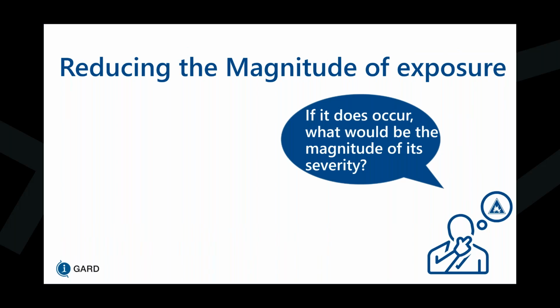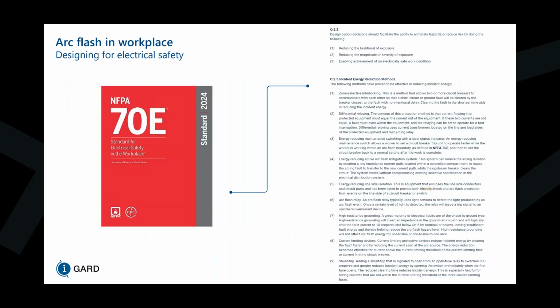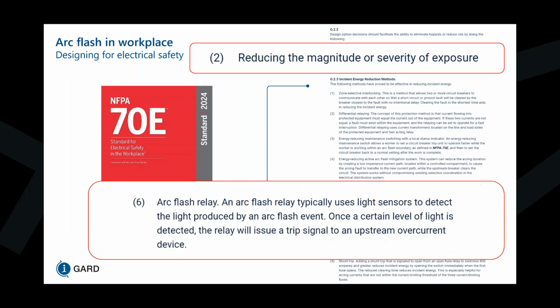So let's take a look at how we can reduce the magnitude of exposure. Of the 9 incident energy reductions listed, we chose the arc flash relay. Arc flash relay typically uses light sensors to detect the light produced by an arc flash event. Once a certain level of light is detected, the relay will issue a trip signal to an upstream overcurrent device. So what we're trying to do here is reduce the exponential upward movement of the power or energy associated with an arc flash incident by cutting off the power upstream such that the arc doesn't build up as fast.